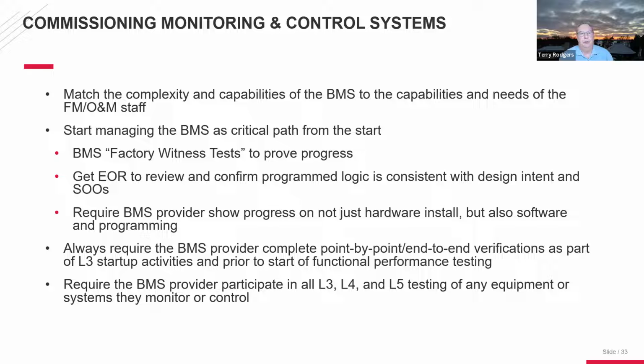But you can basically build that system, and there's really no extra effort, because when it's built you just relocate it into the field, hang it on the panels, replace the 1 foot cable with the 100 foot cables, and reactivate your system. By doing this, you can also require them to demonstrate to you the sequence of operations and the programming.